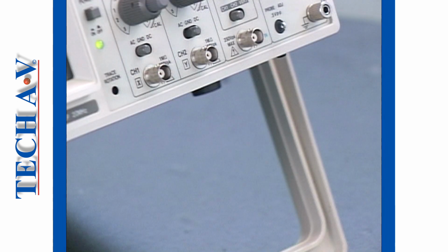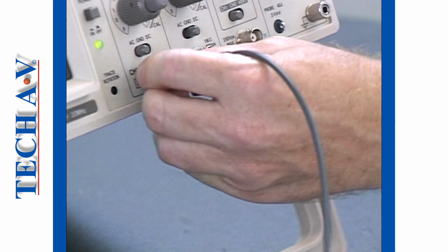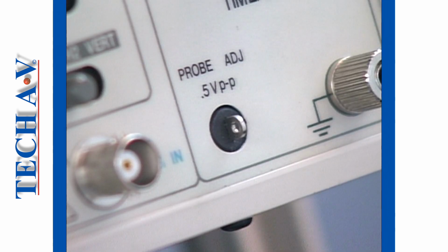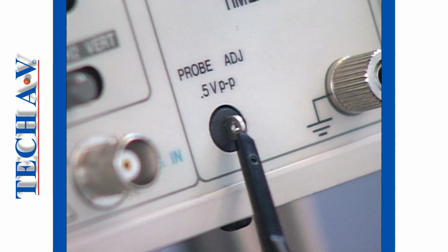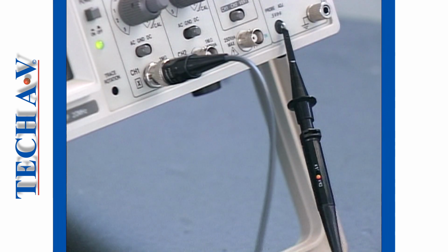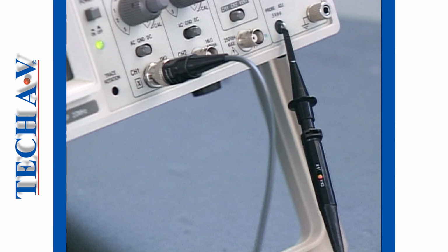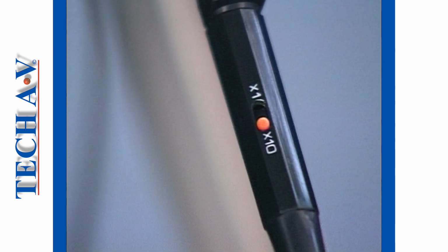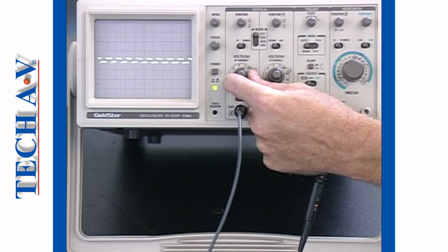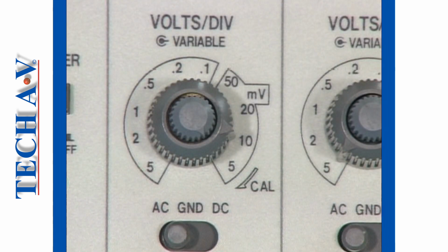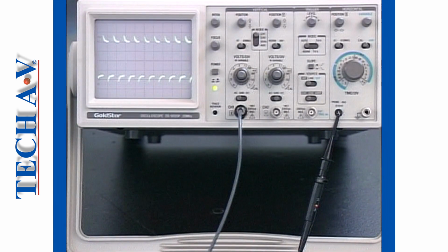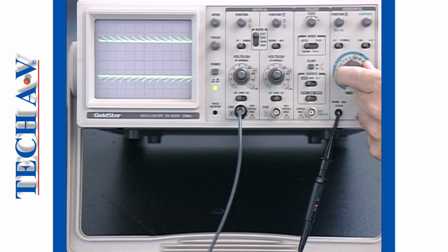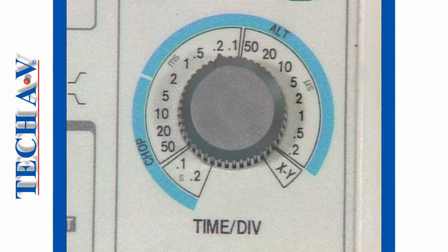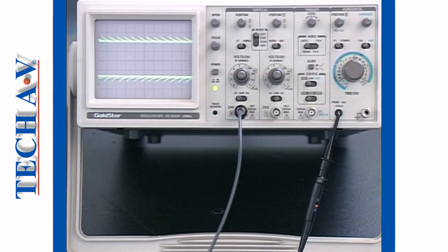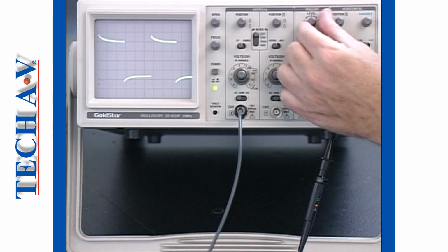Begin by connecting the BNC connector to the channel 1 input of the scope. Connect the tip of the probe to the probe adjust test point located within the horizontal time-based section of the control panel. Set the attenuator on the probe to ×10. Set the channel 1 volts per division control to the 10 millivolt position. Set the time per division control to the 0.2 millisecond position, and adjust the trigger level control, if necessary, to stabilize the trace.